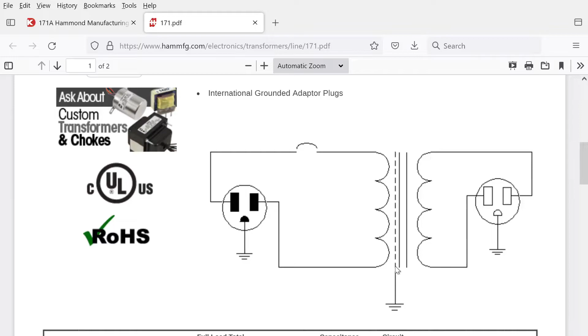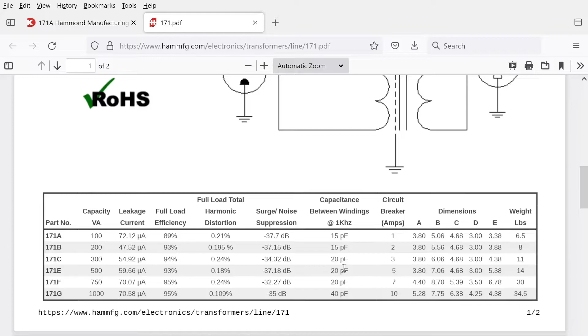Usually a good place to look is electrical suppliers, like DigiKey. If you look at the specs, you'll often see a circuit diagram showing the windings are completely isolated, with some indication that it meets a particular isolation standard. Some are even rated to a higher standard meant for hospital or other medical uses, where you really have to be sure about low currents so you don't accidentally zap anybody. So if you're looking for isolation transformers, be very careful that you get the right one. It might even be good, when you get it, to do some simple testing - which we can perhaps cover in another video - to confirm it's actually isolating, and isn't one of the ones meant to condition electrical power supplies without providing true isolation.